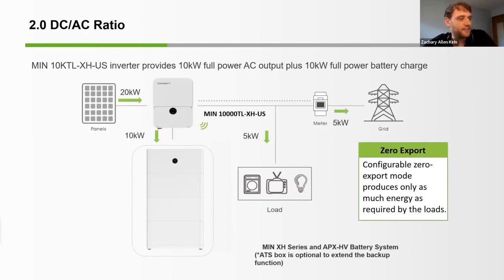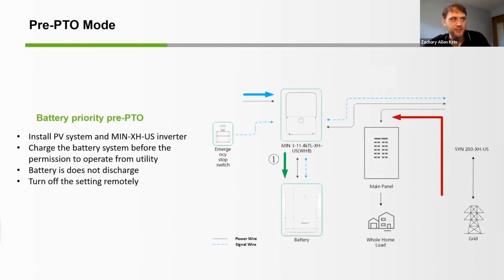Yes, and of course, we'll talk more about the ATS and the SYN devices a little bit more in some other slides here. But first, I'd like to mention the pre-PTO mode. This is another really nice feature that we've implemented. The MIN inverter has a pre-PTO function to allow the inverter and battery system to be installed before the interconnection approval was granted by the utility. In the pre-PTO mode, the battery is charged with solar energy and does not discharge until the setting is turned off.